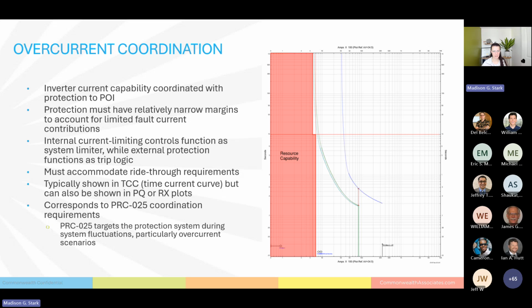And what we see is it has a 120% overage, that's within that 1.1 to 1.5 per unit, that it can sustain for 10 seconds. So that full overage has to be outside of the protection system, because we want that to be able to be fully pushed through. And that's exactly what we see. So these are the feeder relays and then the upstream relay from them. And these feeder relays are appropriately coordinated to not impede the inverter's internal control system and output capability. So in accommodating this overage, this is what accommodates the ride-through requirements and fault requirements of the inverter systems.